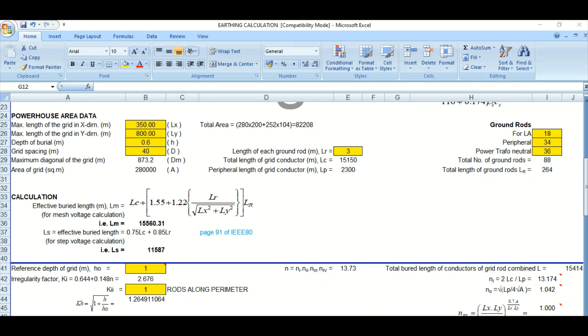Now coming to the step and touch potential check as per IEEE standard to design the underground ground grid. This is the powerhouse data: X-direction by Y-direction is 350 meters by 800 meters — LX and LY. You can change the values highlighted in yellow. The depth of burial is 0.6 meters (600 mm from surface) where the main ground grid will be laid. Grid spacing is considered as 40 meters — all these four values are variable input parameters you need to provide.